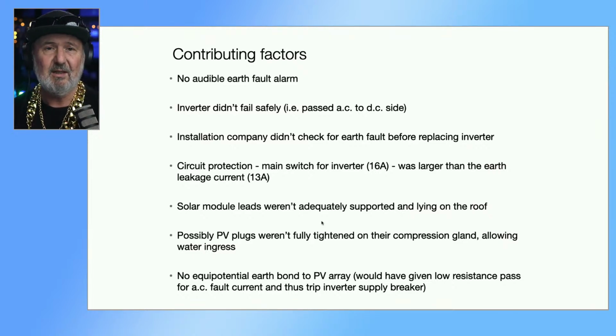It's the right size for the cable as well, because there's different size DC PV array cables. And also, if you haven't pushed home the plug and socket till it goes click, that magical click sound means that the O-ring is actually fully sealed, you're going to have moisture ingress. And no equipotential bonding on the array meant that even when there was a slight leakage, the inverter couldn't detect it because it couldn't find a solid earth resistance point. So it wasn't until it touched onto the roof itself that it triggered this. And that's what we call a bolted fault.